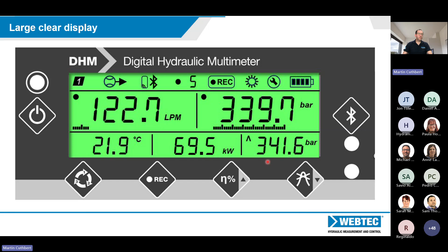And then the largest numbers are reserved for the actual flow and the pressure. The units of measure can be changed by the user when they switch on the device. They can switch between litres and gallons, for example, between bar, PSI, kilograms per centimetre squared, and megapascals. That's also true of the peak pressure that's held here, the temperature of the oil, and then there's a dynamic calculation there of the power in kilowatts or in horsepower, depending on the units that you select. And then you can select the second screen, which gives you the opportunity to measure volumetric efficiency, and the third screen is just to look at the test results that you've recorded. And all of that's controlled using these buttons across the front here.